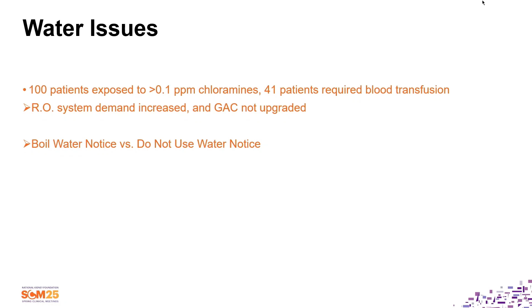So what happens if we receive a boiled water alert in your facility? Do you stop dialysis? No, because the RO membrane and the pretreatment are more than adequate to purify your water to AAMI-level product water. But in a do not use water alert, a contaminant that could harm our patient may not be removed by the RO membrane because we don't know what it is, and it can get to our patient. So in a do not use water notice, you stop dialysis.